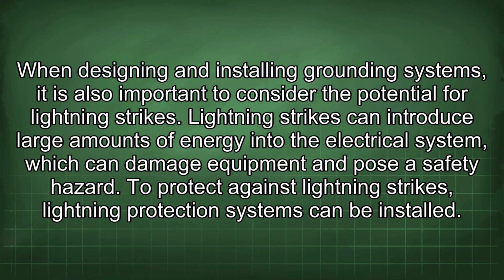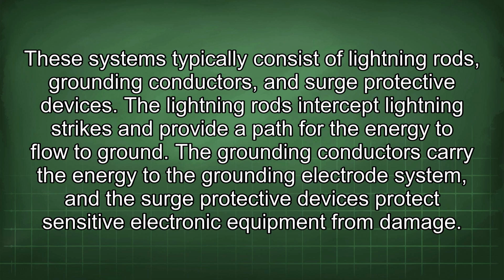When designing and installing grounding systems, it is also important to consider the potential for lightning strikes. Lightning strikes can introduce large amounts of energy into the electrical system, which can damage equipment and pose a safety hazard. To protect against lightning strikes, lightning protection systems can be installed. These systems typically consist of lightning rods, grounding conductors, and surge protective devices.